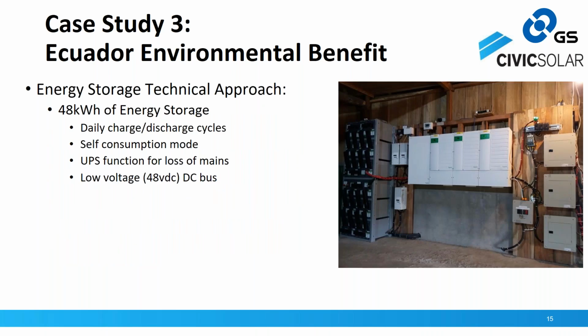We were able to handle that by deploying a relatively smaller system. We used the GS battery in their SLR nanocarbon format, which comes in a 48 kilowatt-hour chunk, 1,000 amp-hours per cell, 2-volt cells. Wired up at 48 volts, you get 48 kilowatt-hours, 33 of which are usable on a daily discharge. We used one of those banks with a 3-phase Schneider system to handle all their daily loads, consume a lot of solar, and reduce their diesel run times to zero.